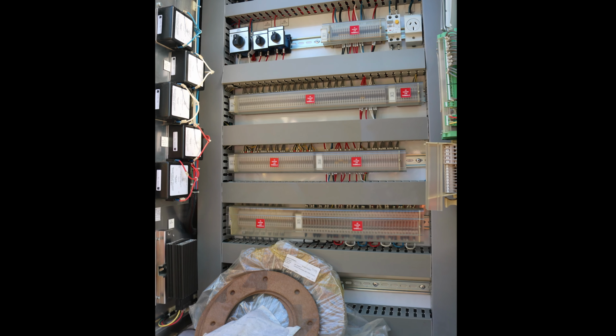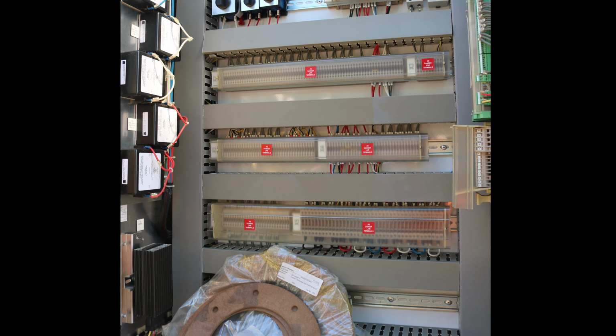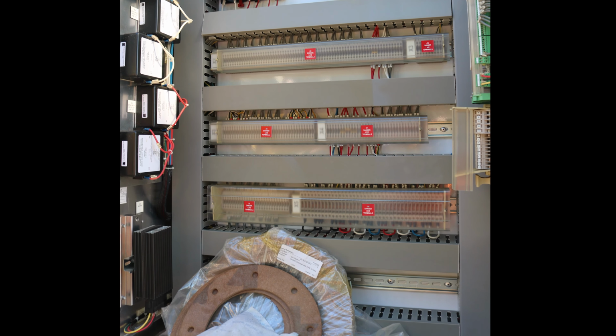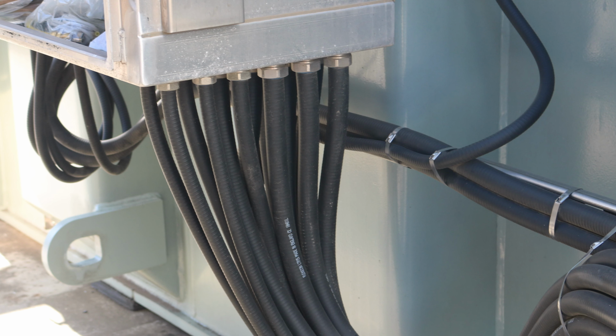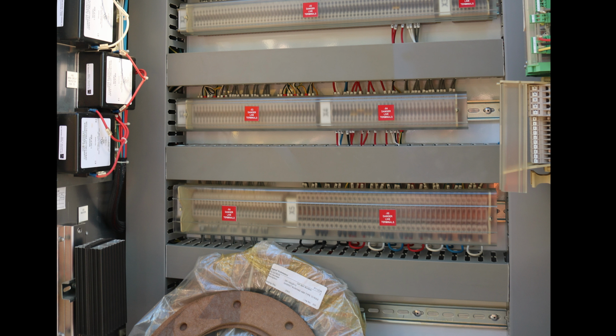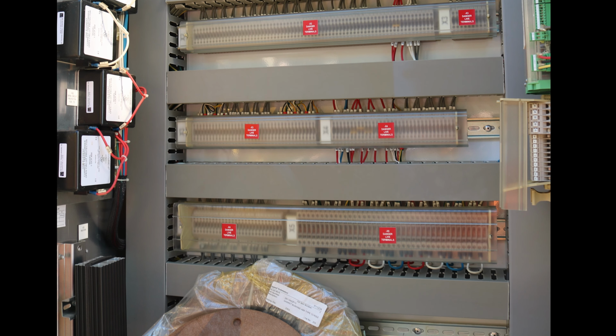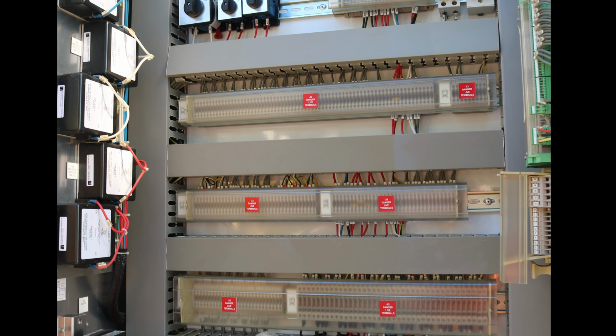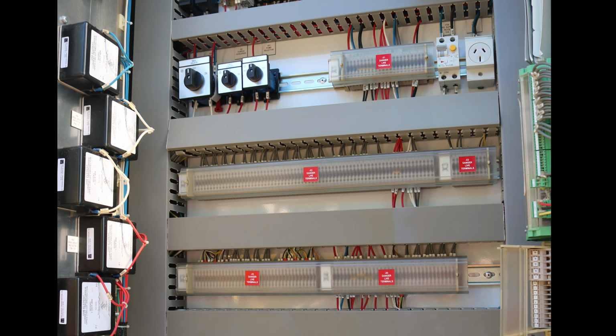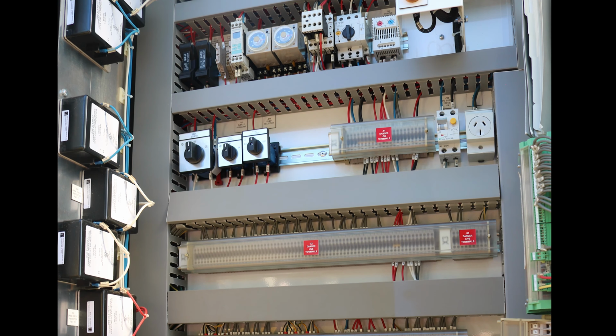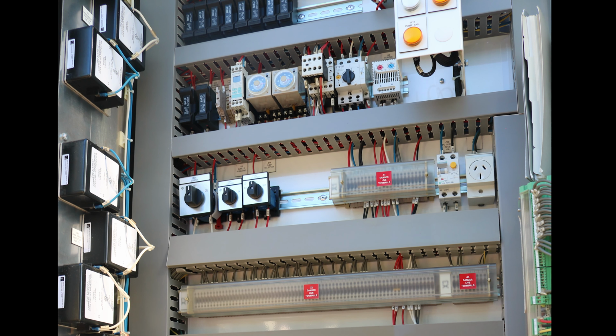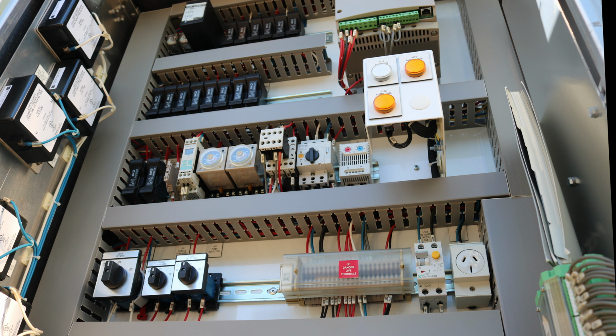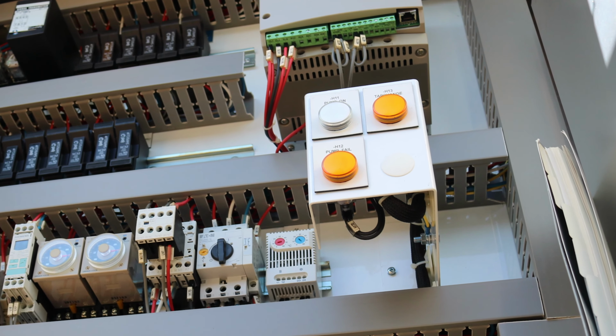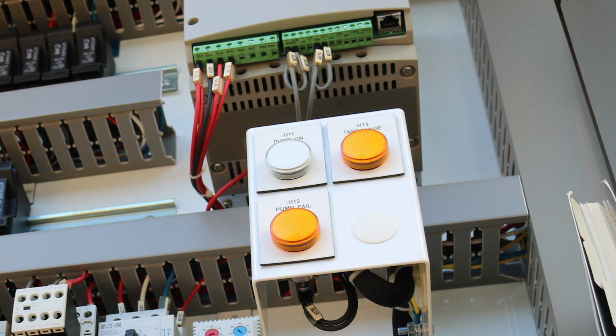So a power transformer is a pretty complicated piece of equipment, and there are a number of ancillary systems that exist on the transformer to keep it operating. The transformer actually will take a 240 volt supply to operate things like the oil pump, to operate the tap changer. There's various lighting. There's power for the oil temperature indicator and winding temperature indicator. All that sits within this cabinet here. There's a number of terminal rails for the different control systems and power systems that are on board the transformer. There's also a number of manual controls here as well to initiate the pump to operate, to initiate the tap changer to operate, and there's also a protection scheme to monitor the 240 volt system inside the transformer as well.